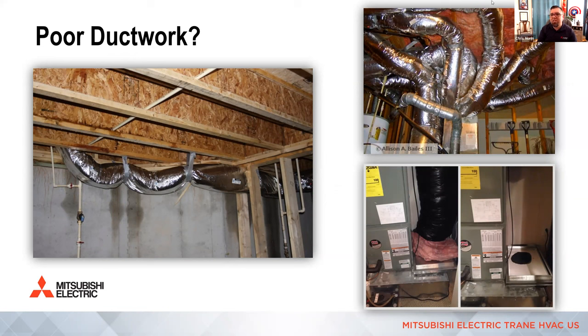Andy said, can trunk size match the supply collar dimensions on an SEZ? Yes, it can, but it's at the maximum. And with low static air handlers, typically what most people do is make a box and just take the takeoffs off the end of the box, 10 or 12 inches in depth, because you don't want to have big pressure losses and you don't have the static pressure to overcome that. So most people don't, but yes, you can.